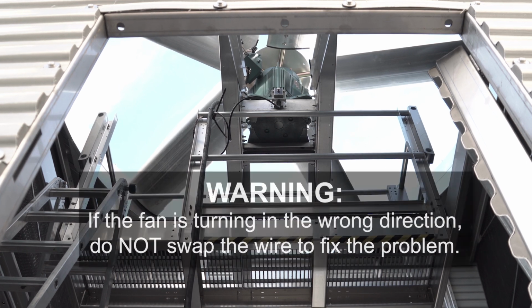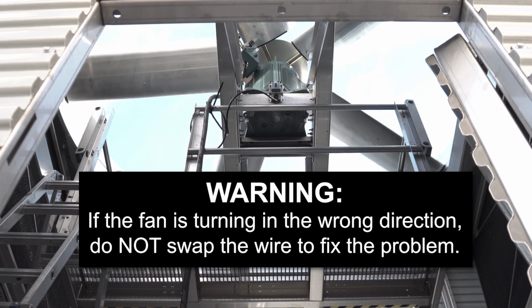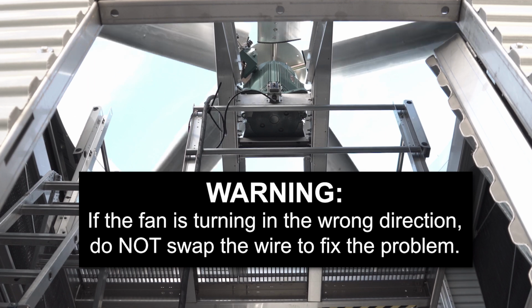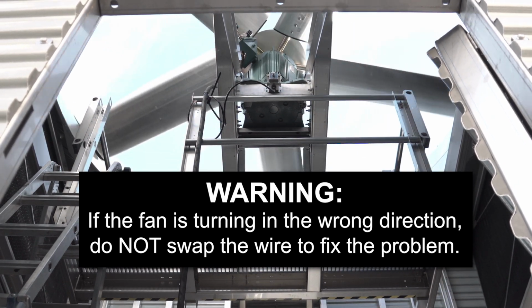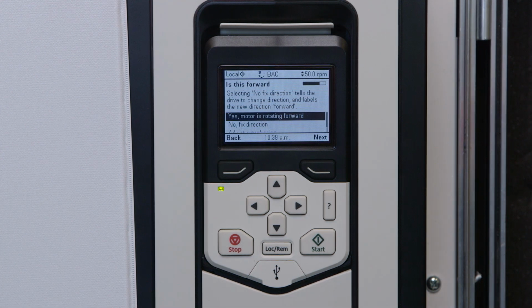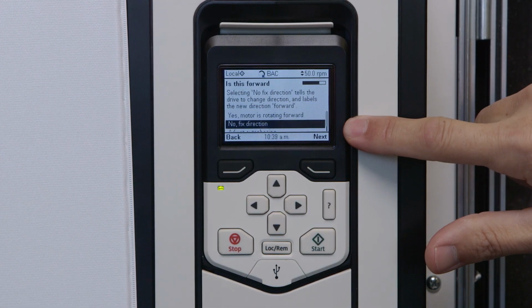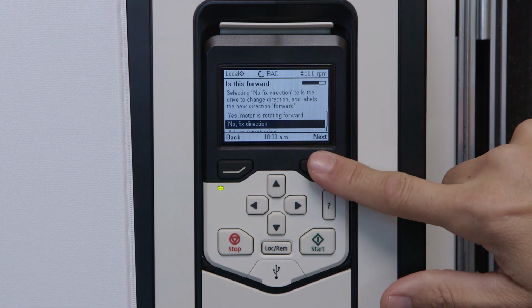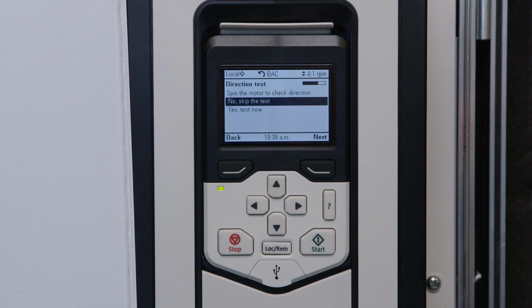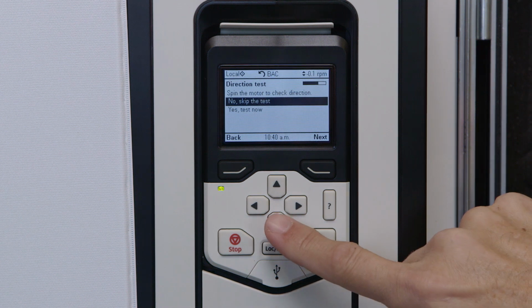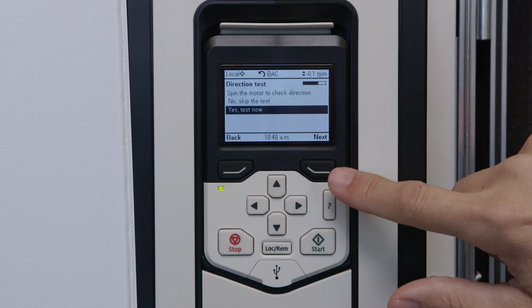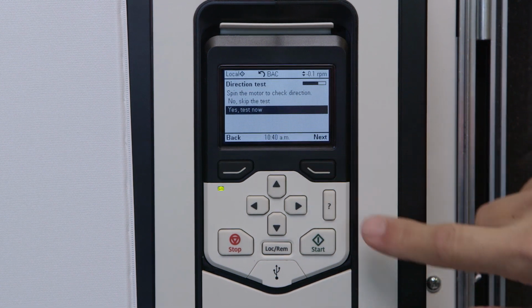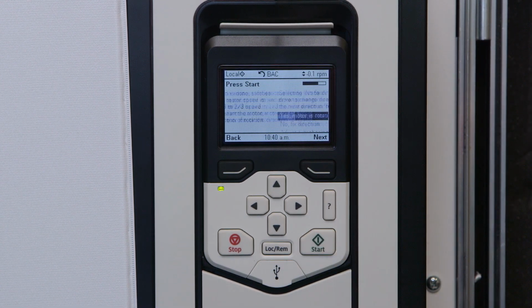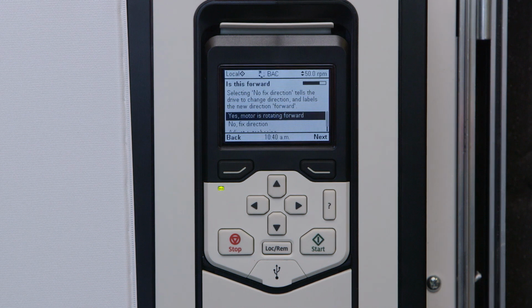If the fan is not turning in the right direction, do not attempt to manually fix this by swapping wire phases. By following the next steps, the unit automatically adjusts the direction inside the VFD. If the fan is not turning in the correct direction, scroll to select No, Fix Direction shown on the display. Then press Next. Repeat the direction test. Press the down arrow to select Yes Test Now. Then press the Next button. Press the green Start button. Then have the assistant check to confirm that fan blades are now turning in the proper direction.